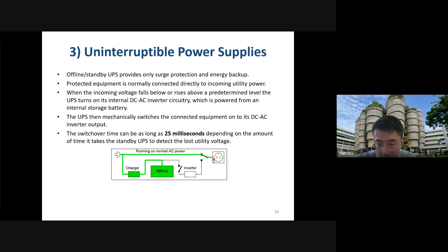And suddenly, if there is an outage, or if there is a kind of power quality issue in the main power supply, immediately the battery and the inverter should switch on and take over the power supply to the load. So this whole process should be very fast. Otherwise, the load will still experience certain blackout time. Especially for data centers, for semiconductor manufacturing, for high accuracy equipment, we have to make sure this switching time is short. You can see that the commercial products can achieve 25 milliseconds. They can take over the power supply in 25 milliseconds. So we have to use such high responding power source and inverter to design this UPS.